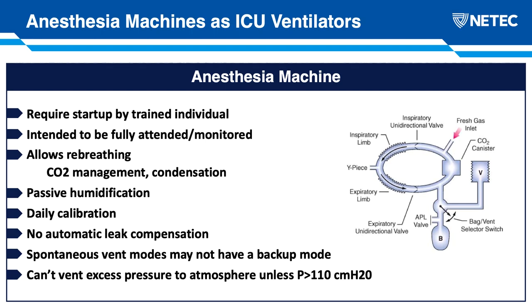So it's an important thing we've got to keep in mind as we move through the considerations of putting these into prolonged use. Another difference is that unlike a lot of our sophisticated and even mid-grade ICU ventilators, our anesthesia machines, because they're meant to be continuously attended, don't have an automatic leak compensation function. They will often alarm at you when they detect a leak, but they don't have the ability to increase flows to compensate. A similar limitation is that when we think about the spontaneous modes of ventilation with which an anesthesia machine can be programmed, most of them don't have an automatic backup, meaning that if a patient experiences apnea, again, the machine will alarm at you, but in most situations, it will not default back to a backup mode. Now, there are some manufacturers and some modes within these machines that are available, typically for an enhanced purchase price. So some of our anesthesia machines, in fact, do have the backup mode, but you'd want to be very familiar with the modes that were available to you and whether or not this feature was present.